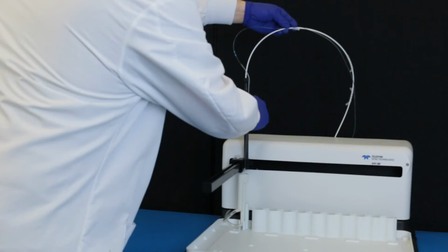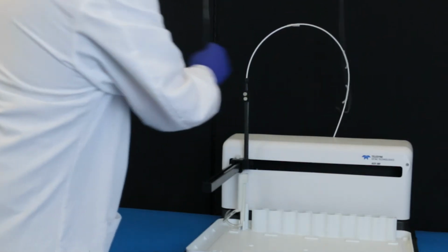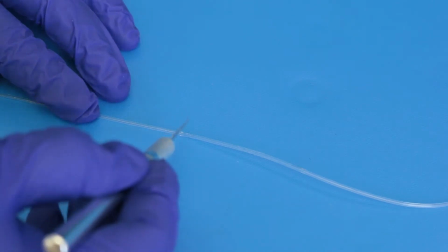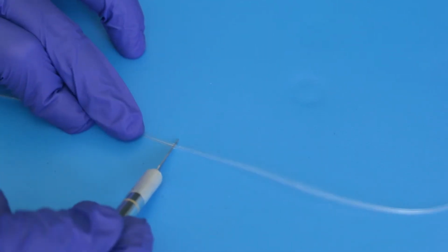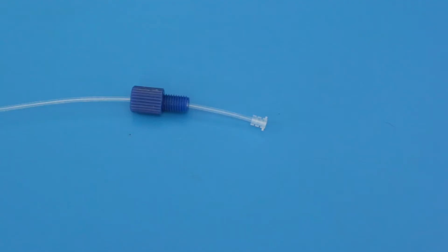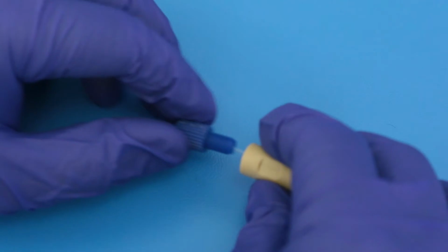The tubing should be long enough to allow the sample probe to move easily up and down, even in the far corner positions. You will trim the tubing just past the spiral wrap. Cut the tubing. Next, slide the blue fitting and ferrule onto the cut tubing. Use the tubing coupler to seat the ferrule.